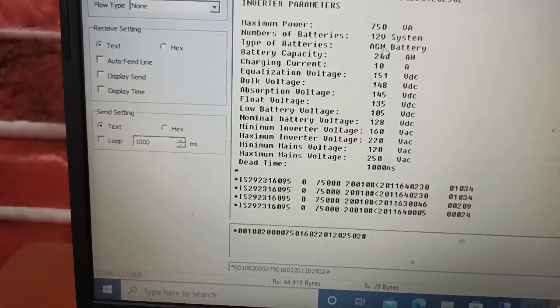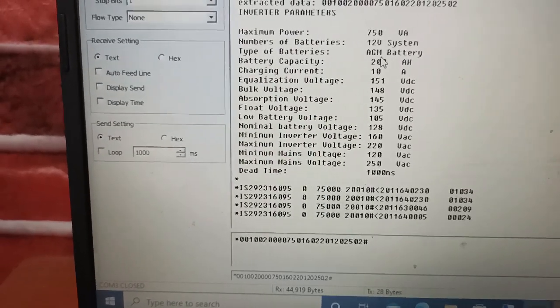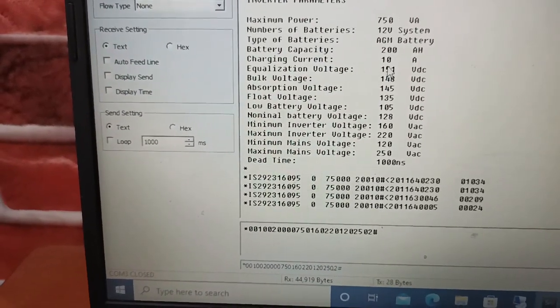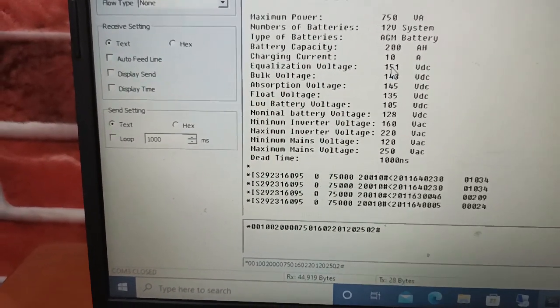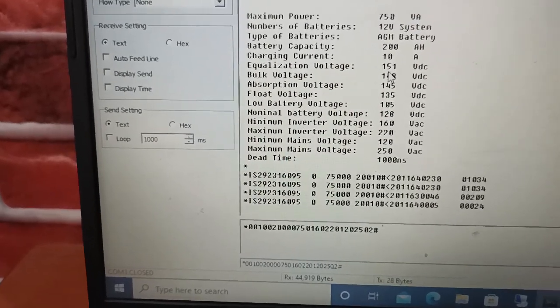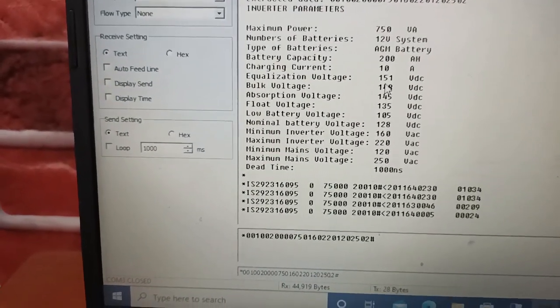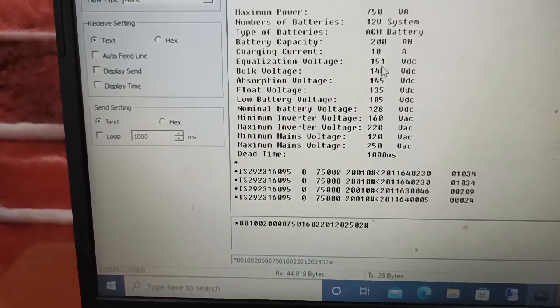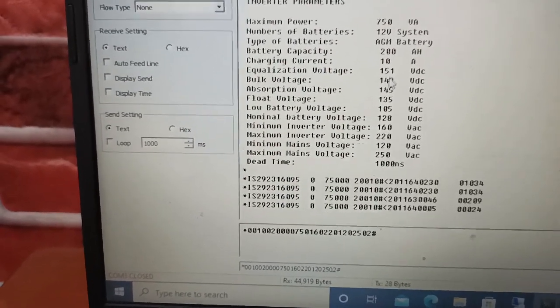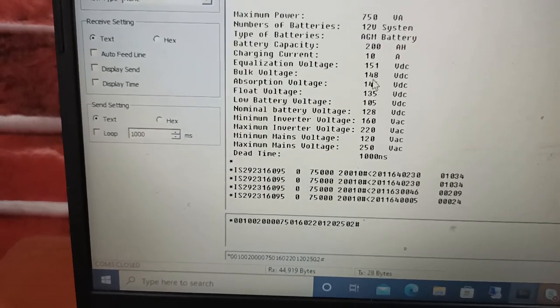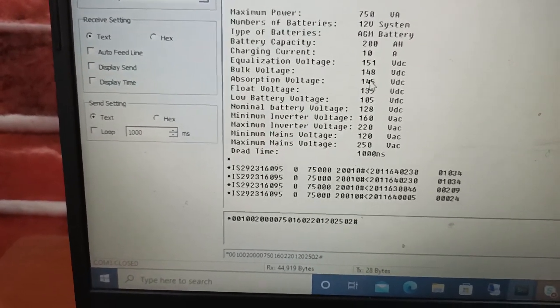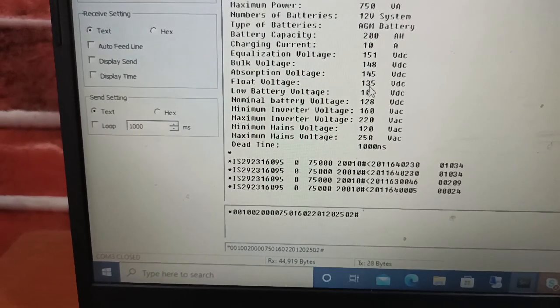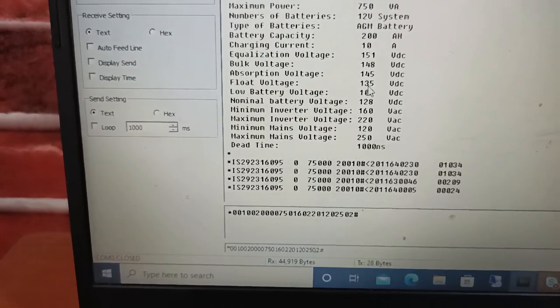I will say that it's a 12-volt system. The type of battery is AGM. Battery capacity is 200 amp-hours. Charging current — we want to charge the battery at 10 amps. Equalization voltage — I won't implement the equalization process, but in future it's supposed to be 15.1. The bulk voltage is 14.8. Absorption voltage is 14.5.